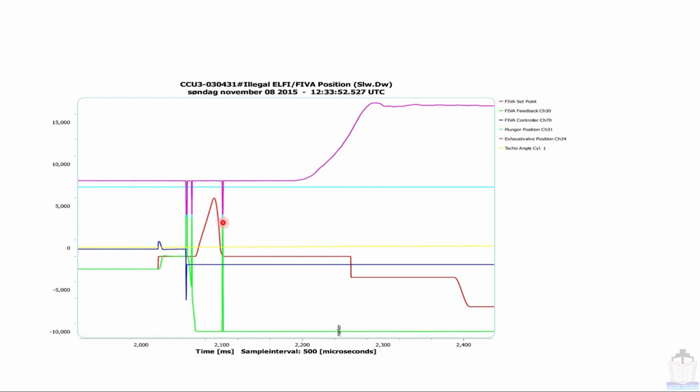Also channel number 30 is generating the signal wrong at the same point, while channel number 70 is looking almost okay. So these two graphs are erratic at the same point. It is possible only if wiring has some problem, or MPC channel number 30 and channel number 34 are defective, or the MPC is defective.